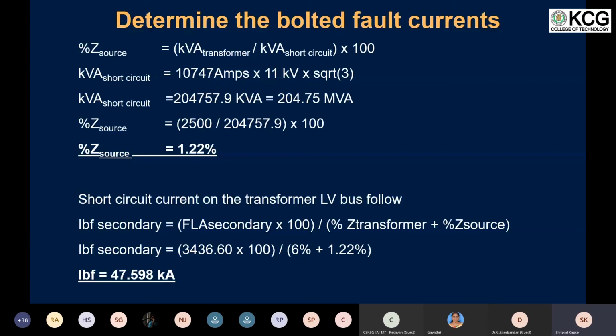And just from an academic point of view, I also worked to identify what the incident energy level could have been if the arc flash protection was not in the picture. In that case, the relay would operate on an IDMT based time coordinated system. To do that, we identified the maximum bolted fault current, and I have provided the calculation here. We used the kVA of the transformer and the short circuit kVA levels, and then found the percentage impedance, and using that source percentage impedance we found the maximum bolted fault current. As per our calculation, the bolted fault current level on the 415 volt switchboard could have been up to 47 kiloamperes.